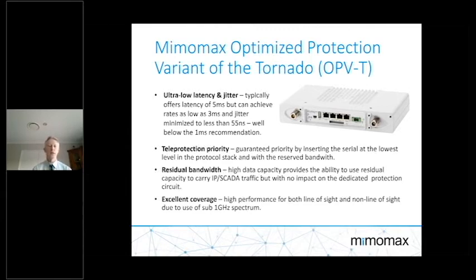We talked about guaranteed priority by inserting the serial at the lowest level in the protocol stack and reserving that bandwidth, so never allowing the Mimomax or the IP side to encroach on the teleprotection piece.